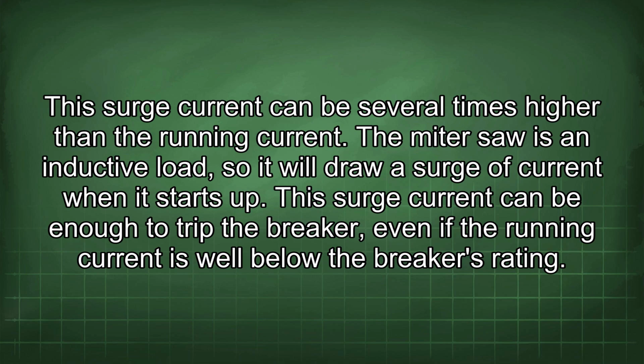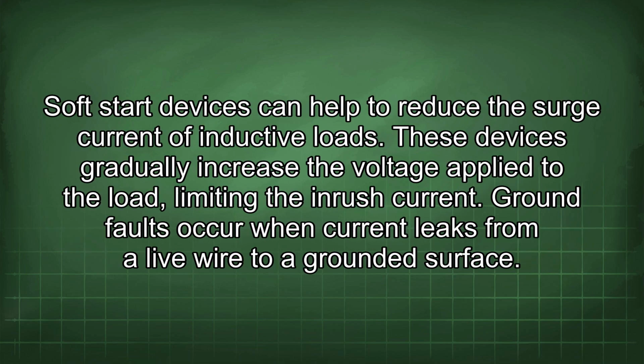This surge current can be enough to trip the breaker, even if the running current is well below the breaker's rating. Soft start devices can help to reduce the surge current of inductive loads. These devices gradually increase the voltage applied to the load, limiting the inrush current.